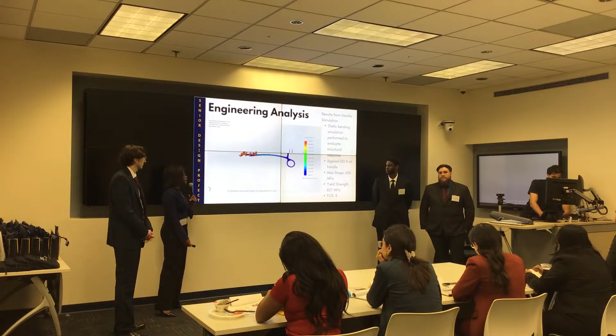Thank you, Destiny. So as per three of the critical verification protocols we completed, we wanted to ensure that the spacing was accurate and controlled when being combined with the cradle and the use of our dual applicator. Additionally, we wanted to verify that the dual applicator actually reduces the time it takes to place the clips accurately onto the vessel. As for the accuracy trial, we did 10 trials per measurement. So we did one for each of the spaces in the cradle, and we did one with a single applicator as well. And we did it with just the dual applicator, and we verified that all of the placements were within a 0.1 millimeter tolerance. So that verification trial was passed.